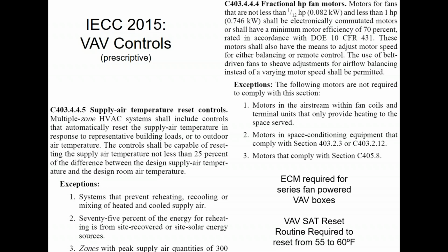Talk about these two together. If you have small horsepower fans on your fan coils and series fan powered boxes, you need to control them with an ECM. All series fan powered VAV boxes are required to have an ECM, electrically commutated motor. That is a requirement on there. So keep that in mind.